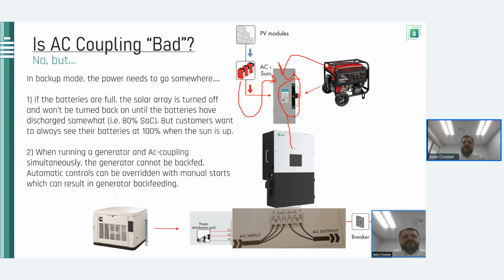You say, now wait a minute, I know that SMA in the past has done simultaneous generator running and solar production. They do solar diesel hybrid camps too, where your solar array reduces the amount of diesel that your generator is using. And the answer is that that works at scale when you have relatively known base loads and relatively known amounts of solar power, and you might just have a small solar array with a large base load, so you don't get into the issues of backfeeding.